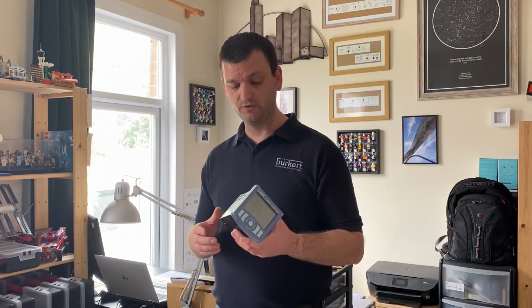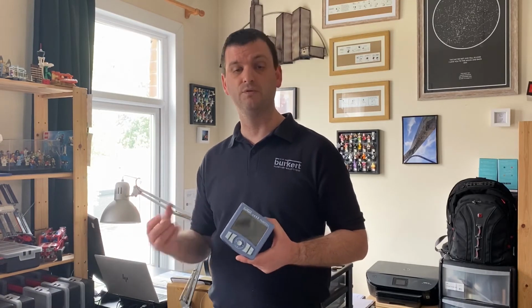Now Type 8619 is much more than just a transmitter. With onboard facilities such as math functions and PID control, we're actually able to turn this into a process controller. We can use those signals to control dosing pumps, to control valves, or alternatively, we can take that pH measurement that our reverse osmosis client is using and use that to produce the control philosophy for controlling the pH dosing chemical. For companies that are just starting out to build small skids, the 8619 is ideal, being able to provide process control functionality without having to have the knowledge of a PLC or a PLC builder on site. This is a great solution.